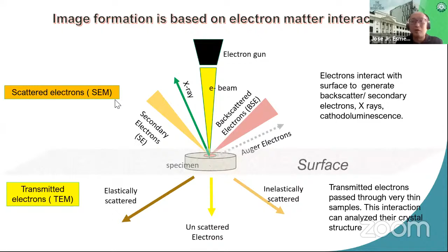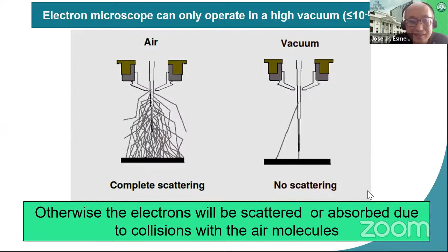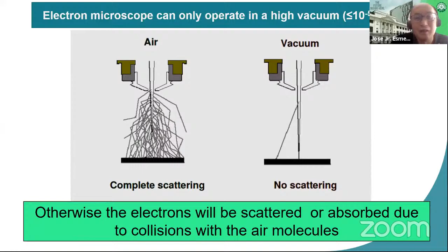So as I mentioned before, electron microscopes work only in vacuum. Why? Otherwise, electrons will be scattered and absorbed due to the collisions with air molecules. Okay, so that's why, as I mentioned before, it's not possible to image live or wet samples. And the vacuum is very crucial. So that's why these instruments have to be turned on 24 hours, 24/7 in order to maintain their vacuum integrity.